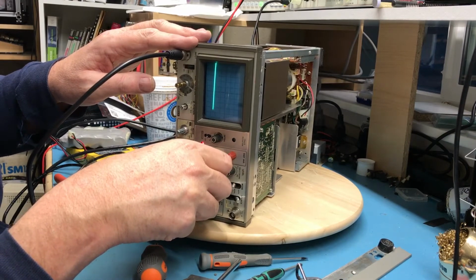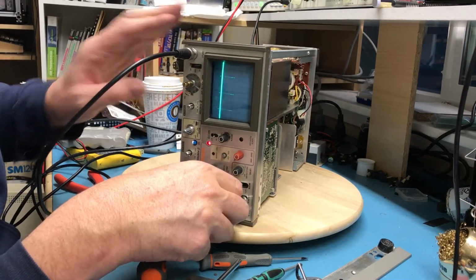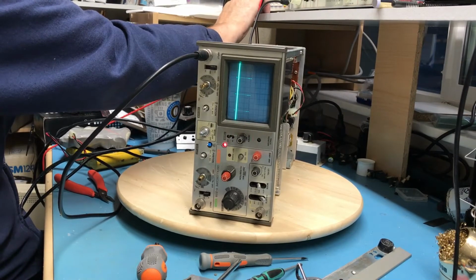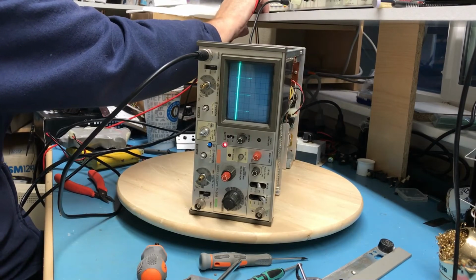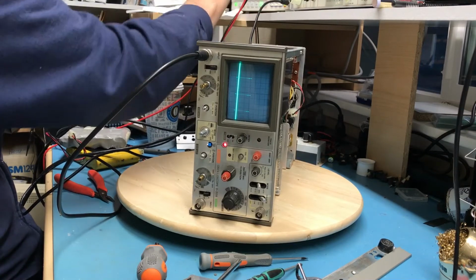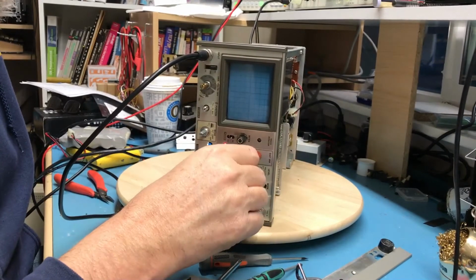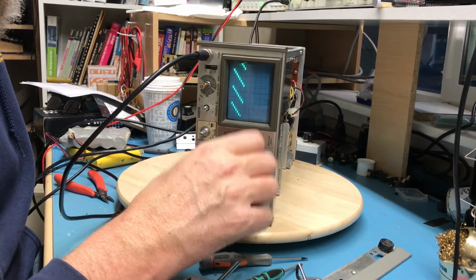I'm actually not triggering well on it, but that's fine. I don't know if you can see that or not, but there's essentially a little pulse train there to emulate a human pulse. Arbitrary edit. No, I don't want to edit. I want to load from the built-in. And we'll do an upward staircase. And that looks very reasonable.